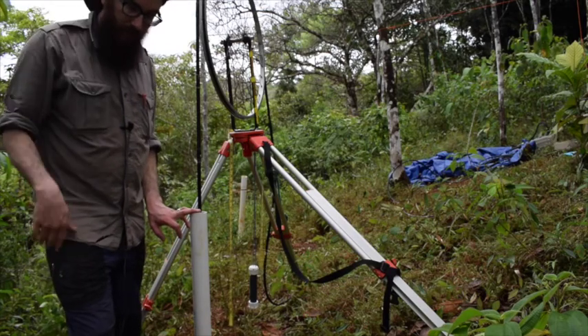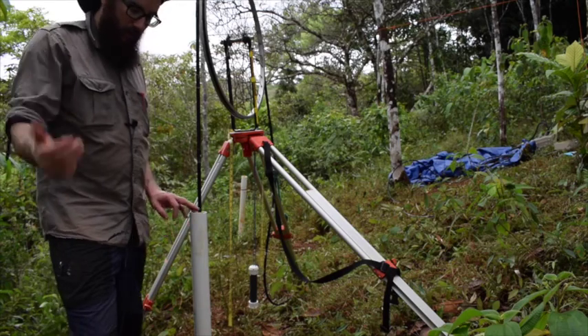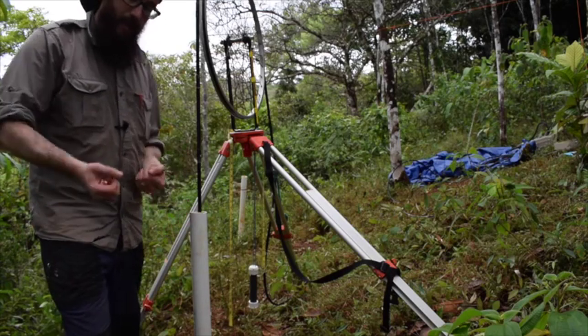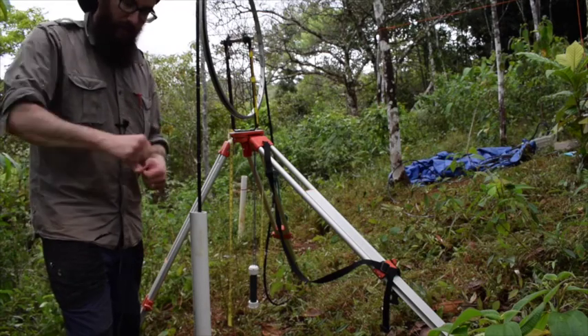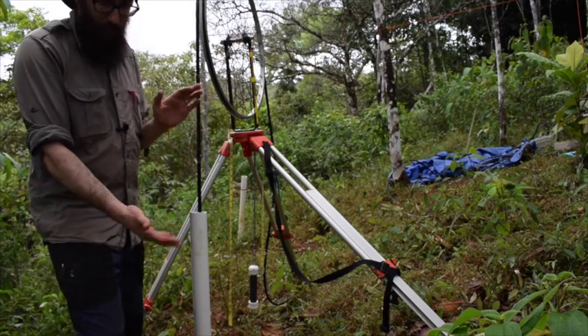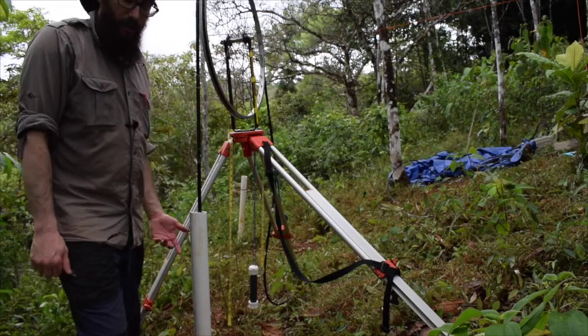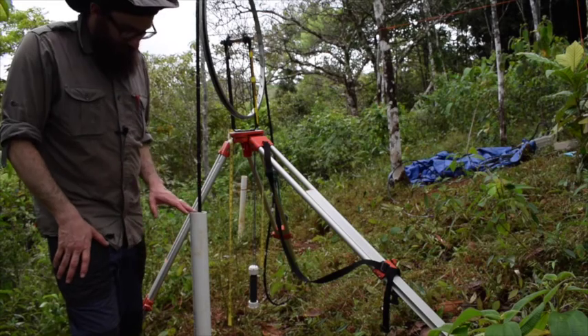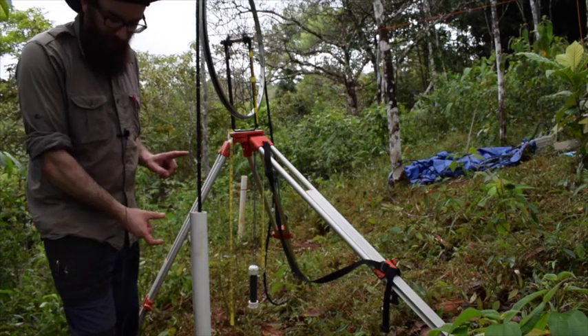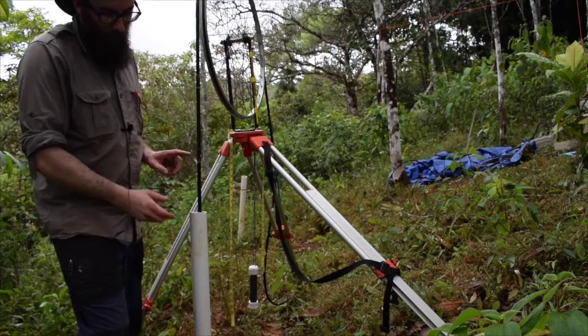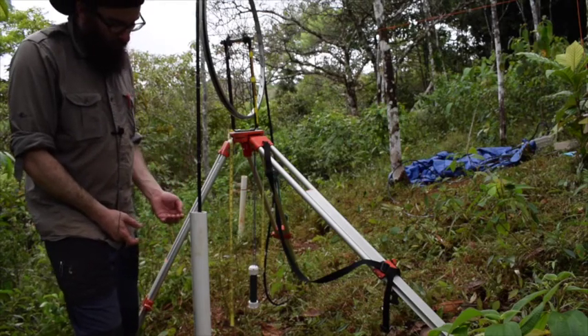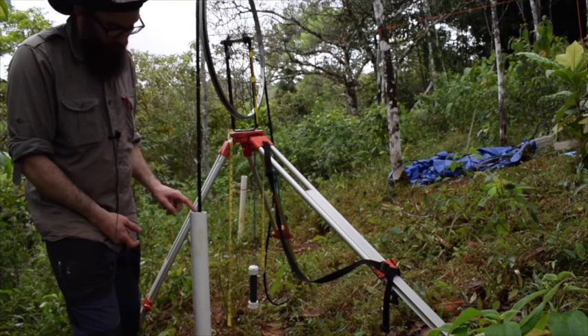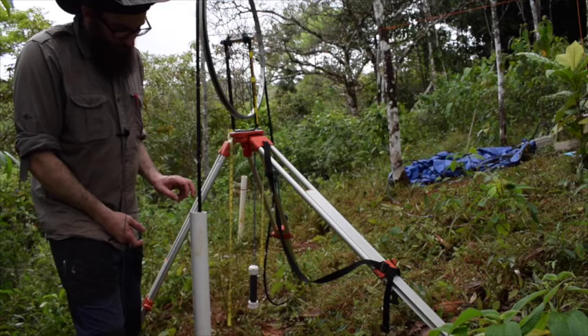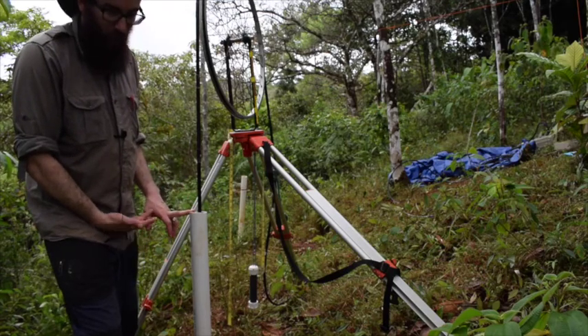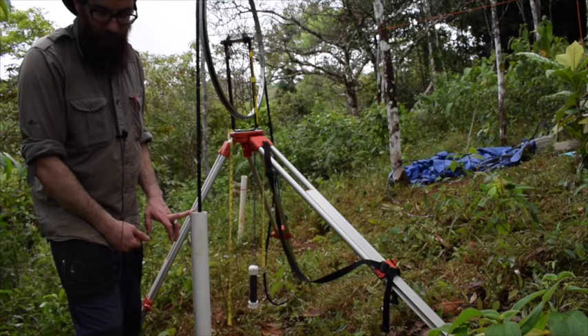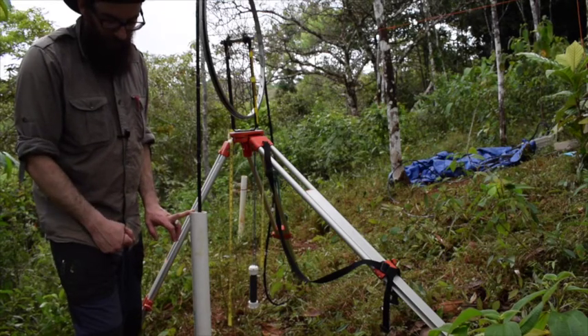So we don't usually use the noise reference cable in remote areas, but you can use it, and it's really obvious. It's just a gray cable. You plug it in on the instrument where it says noise reference cable, plug it into the noise reference cable box, which is just a big gray square box, and then put that in the direction of the noise. The last thing is that it's really the bottom of the sensor that's detecting where the water is, not all the way at the bottom, but just slightly above it. So when you see your sensor start to come out of the top of the well, you want to make sure that the bottom of the sensor is also completely out of the ground, particularly if you're going to be measuring the near surface moisture content, if that's important to you.